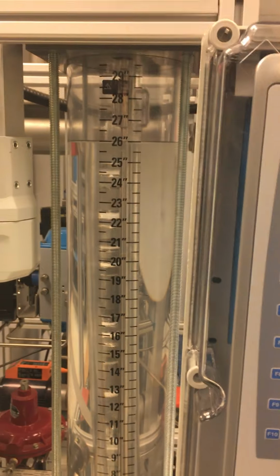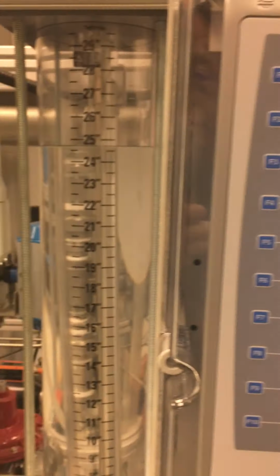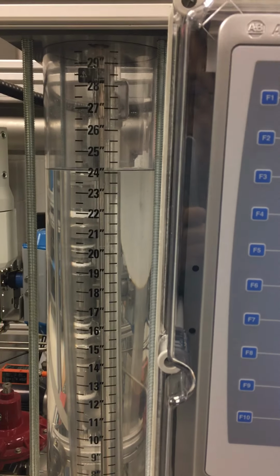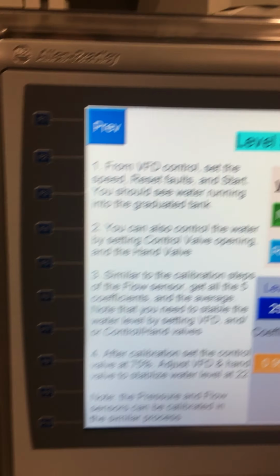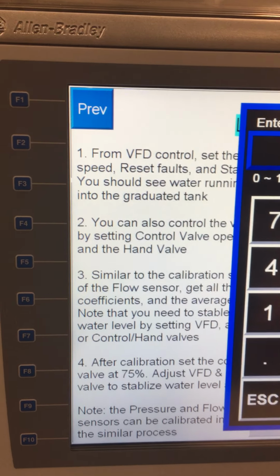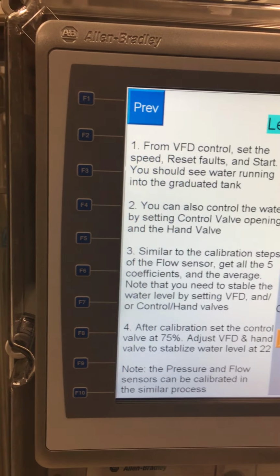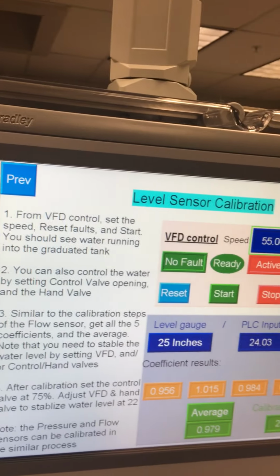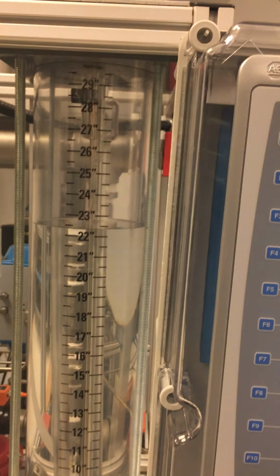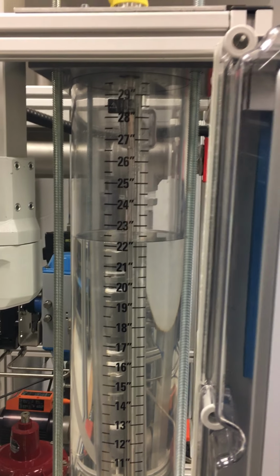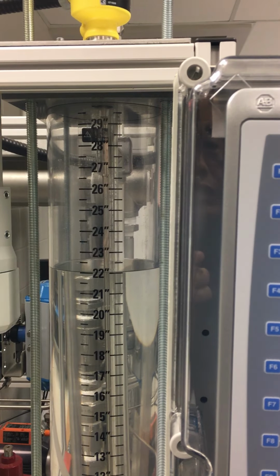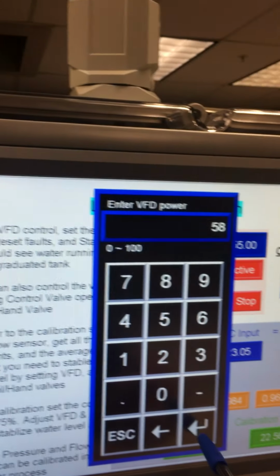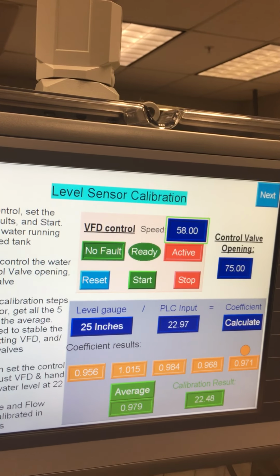The water is dropping. I want to maintain it at 22 inches. So clearly 45 is not good, so I need to get maybe 55. Increase to 55, water level still dropping, but slower. So that means I need to get maybe higher, 58.